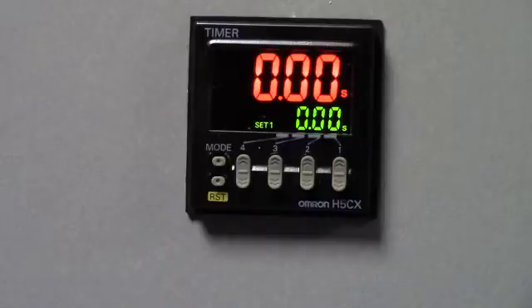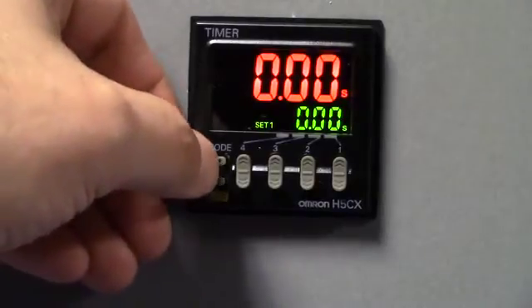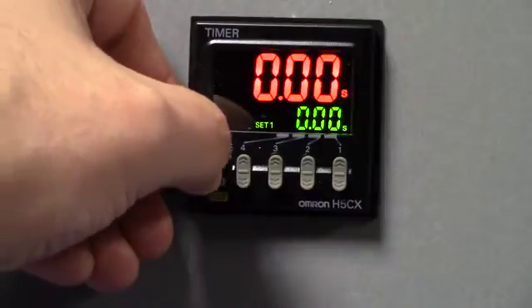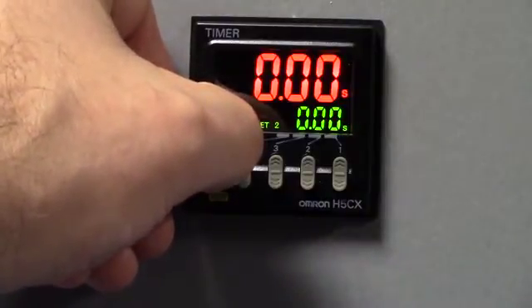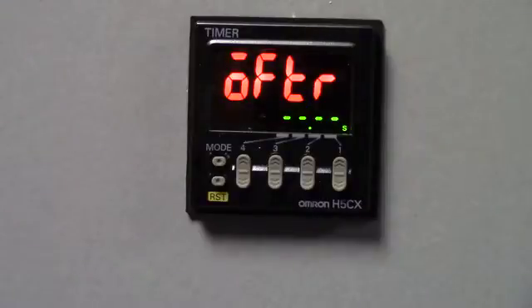Once that is completed, then power up your H5CX-N, and when powered up, it should look like the picture in the video right now, where you have zeros across the board. So what we are going to do now, we are going to press and hold the mode key for 3 seconds. Now we are into the function programming of the H5CX-N. What you are seeing before you right now, this is the setup for the off time in the twin timer.